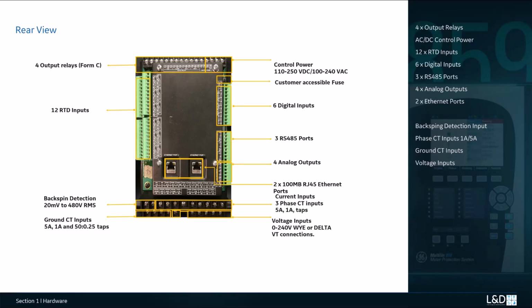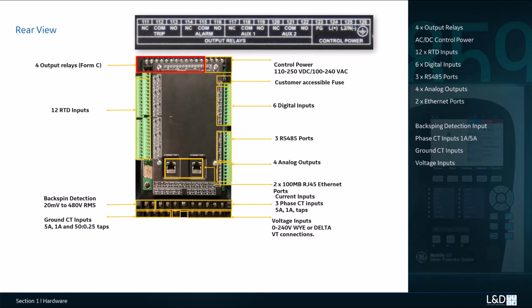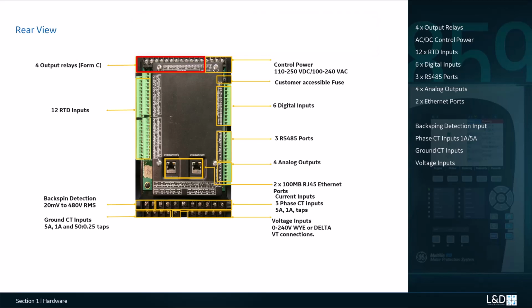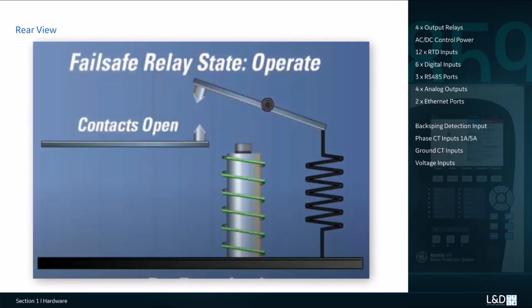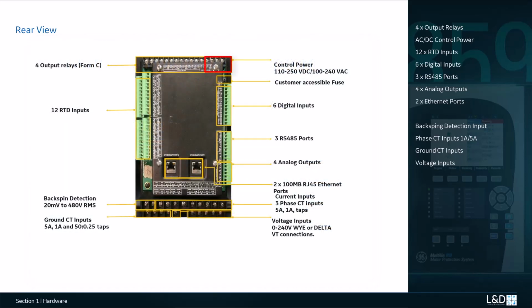On the rear side of the relay, the terminal mapping and placement is exactly the same as the 369. On top are the terminals of the 4 output relays: trip, alarm, auxiliary 1 and 2. They are all Form C relays, which means they can have both normally open and normally closed contacts. They can all be programmed as fail-safe or non-fail-safe relays. The control power input is also on the top terminals. The input range is 110 to 250 V DC or 100 to 240 V AC.